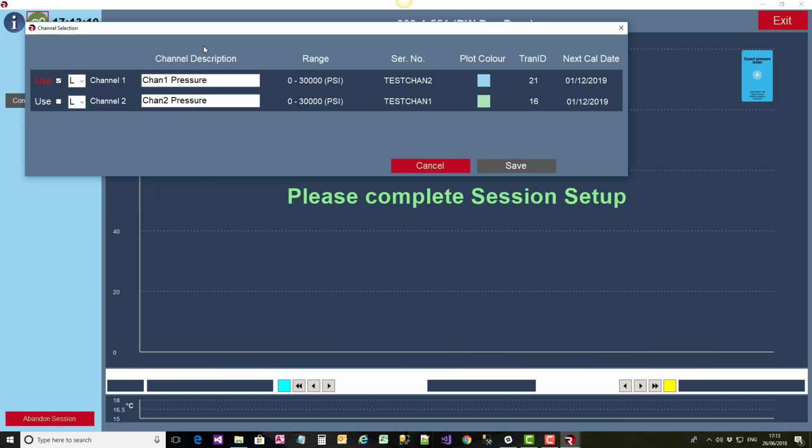The next thing is to choose the channel that you would like to perform the pressure testing on. You can see here on this domain we have it set up so there's two pressure testing channels. There's actually two 30,000 psi transmitters on this test rig. However, you could imagine that this could have one 30k and one 1k transmitter, or perhaps only one 30k transmitter and channel 2 doesn't appear here. There is the opportunity to put up to 4 different pressure transducers on this system, but for now I'm just going to leave it as channel 1.